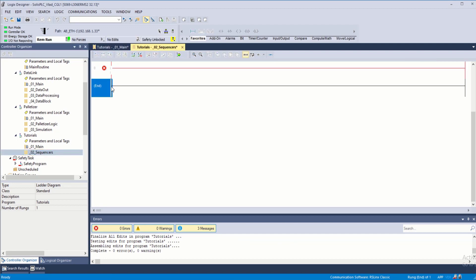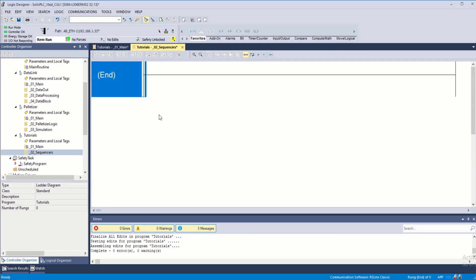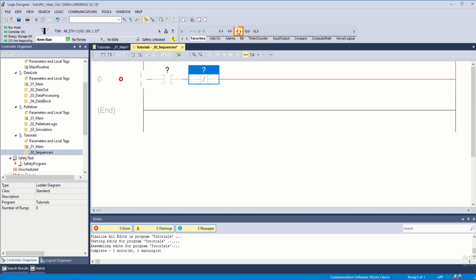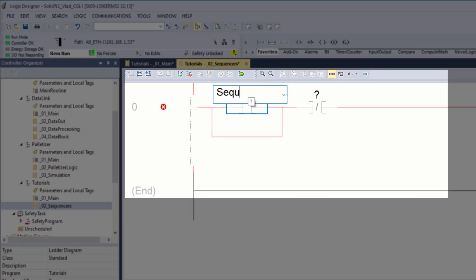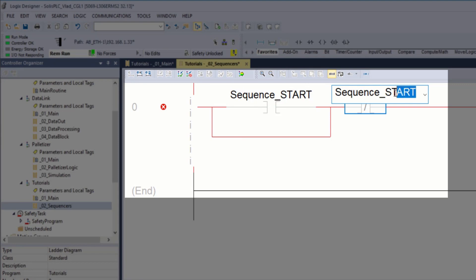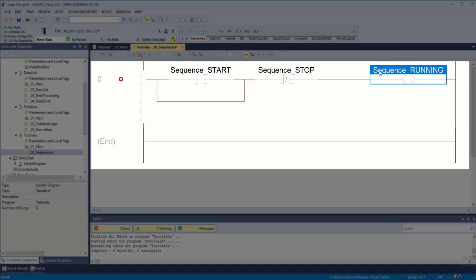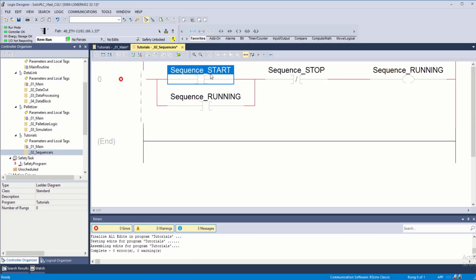Now we can go into sequencers and start adding some logic. A sequencer is nothing more than an array of different steps that the system can take in order to execute properly. At the beginning I'm going to have some kind of a start and stop routine just like we've done in many other cases — a start button, a stop condition, as well as a latch. Once again, as I've shown many times for a motor command. I'm going to call this sequence underscore start, sequence stop, and sequence underscore running.